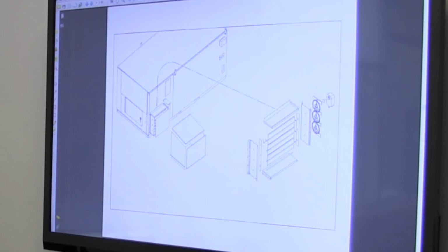What's telling it to switch from heating to cooling? The automated logic controls. So it's some sensor in the zone? Yeah. It has nothing to do with the outside air then? No. Yeah, Zone 10. Right. I'm pretty sure that, yeah, I'm not sure, are they serving the hallways? I'm not exactly sure what zones they serve and what switches them over precisely, but I think they control the discharge air temperature to maintain, say, the hallway temperature, or maybe they blow a little into each room, I'm not sure.